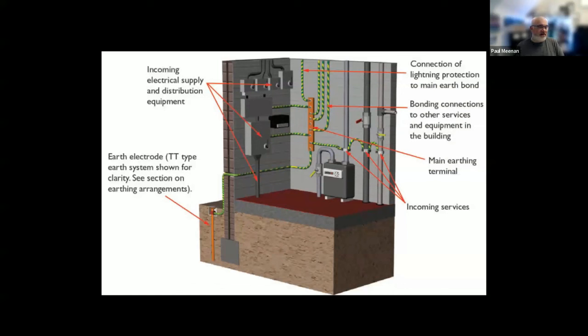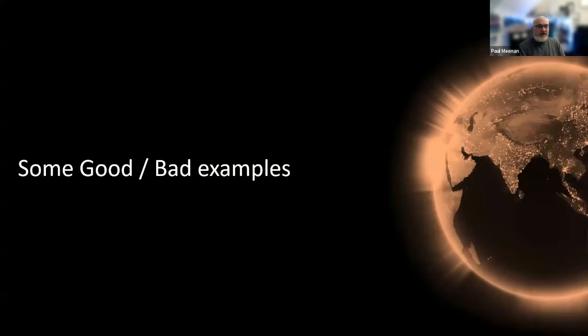So that is a cross-section of an installation where you have the incoming supply cable, the main switch, you have a copper earth bar, and we bond gas, water, other services, ductwork. And sometimes, depending on the earthing, we put electrodes in. There is a requirement or a recommendation now for new installations to have electrodes. That wasn't necessarily the case in the UK. So that's just some fundamentals there on the terminology.